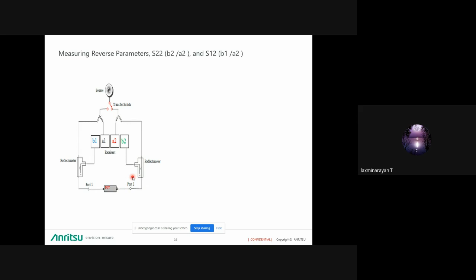So like this, you will be measuring the S22 and S12. And when you come to the VNAs, most of the time you will be talking about calibrations. There are 2 types of calibration: instrument calibration and measurement calibration. The instrument calibration will be performed in the recommended cal interval at a local service center or an accredited calibration center, which ensures that the given specification is met by the instrument, and which will follow some standards like Z540, Premium, or an accredited certificate.